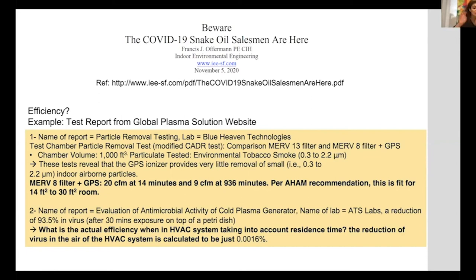But if you install the same equipment in an HVAC system, it can have an efficiency of this type, 0.0016%. So practically it's ineffective, it doesn't do anything. And I start seeing a lot of lawsuits about different types of these electronic air cleaners. So I cannot stress enough, do your due diligence and ask the questions: how is the efficiency translated when I put it in my HVAC system, in my duct? And give me the safety data, actually installed in the HVAC system, via a third-party test. So far I have not found any, and I would be happy to help you vet equipment.